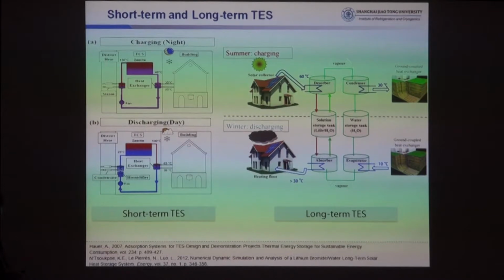But during wintertime, you just let the strong lithium bromide solution absorb water. And in this case, it's connected to the ground source. So sometimes the condensing heat is put into the ground source. In the winter time, the ground source is used to heat the evaporator. In this case, you get some absorption heat released at a high temperature, more than 30 degrees centigrade, for heating the room. So this is seasonal thermal energy storage.